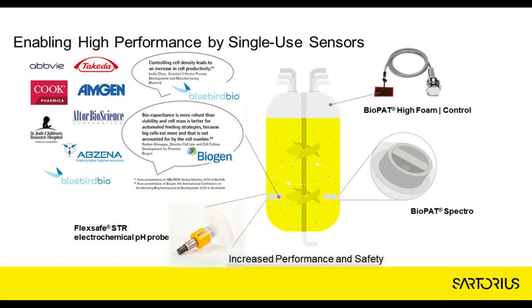Finally, the BioPAT biomass sensor, developed with an ongoing partnership, enables cell densities to be monitored online, reducing the amount of samples taken by operators and overall handling efforts. It's based on radio frequency impedance, measuring capacitance in the media, which correlates directly with cell density.